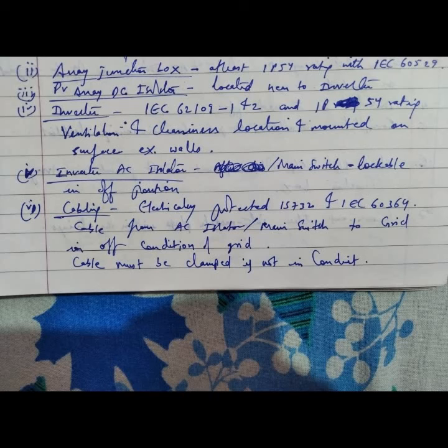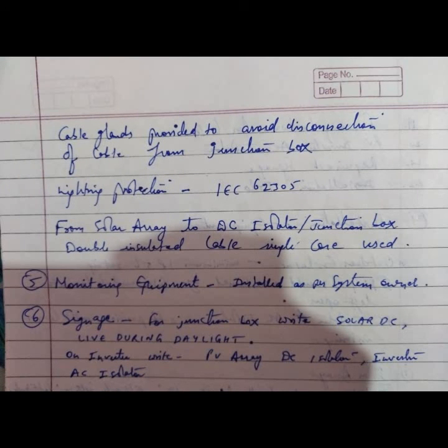Then the array box: IP54 rating, IEC 60529. PV array located near the inverter. Inverter: IEC 62109-1 and 2 and IP54, with ventilation, cleaning location, and mounted on a surface, for example walls. AC isolator main switch lockable in off position if possible. Cabling electrically protected, IS 732 and IEC 60364; cable from isolator main switch to grid in off condition of grid. Cable must be clamped if not in conduit. Cable glands provided to avoid disconnection of cables from the junction box.